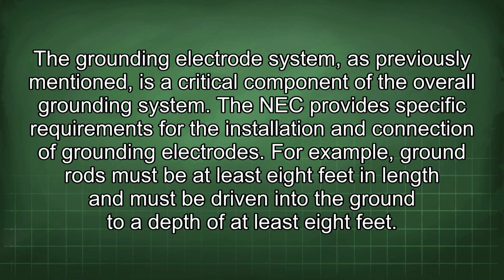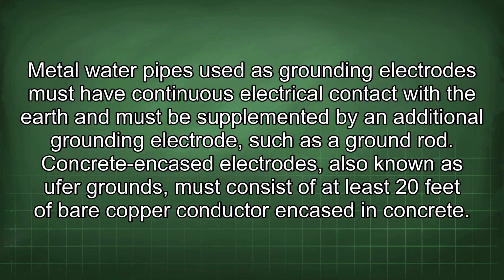The NEC provides specific requirements for the installation and connection of grounding electrodes. For example, ground rods must be at least 8 feet in length and must be driven into the ground to a depth of at least 8 feet. Metal water pipes used as grounding electrodes must have continuous electrical contact with the earth and must be supplemented by an additional grounding electrode, such as a ground rod.